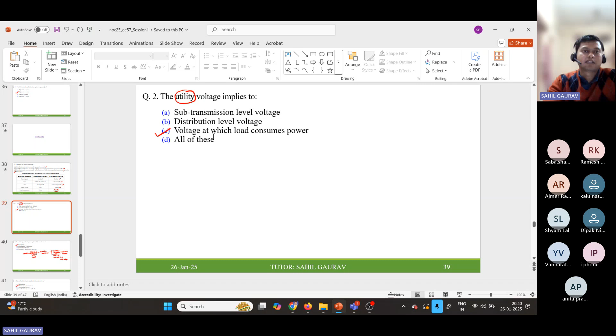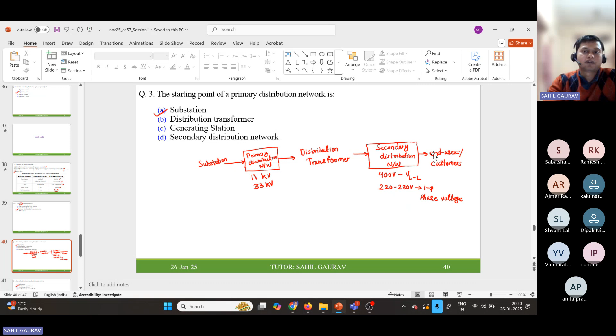The starting point of the primary distribution network is the substation. The distribution transformer connects the primary distribution network, operating at 11 kV or 33 kV, to the secondary distribution network, operating at 400 volt line to line or 230 volt single phase, providing power to individual customers. The end point of the primary distribution network is the distribution transformer. For a radial distribution feeder, the number of nodes equals the number of lines plus 1. In this example we have 3 nodes, so the number of lines is 2.